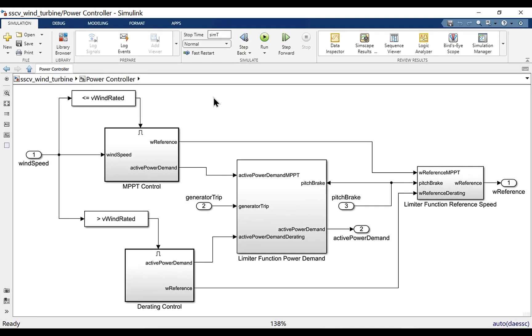The power controller of the wind turbine decides whether the turbine should be in MPPT control mode or it should be in derating control mode. Based on which, it decides the reference rotation speed of the wind turbine and the active power demand which is fed to the turbine generator. Based on which, the generator decides how much torque load should be applied on the rotor hub of the wind turbine.